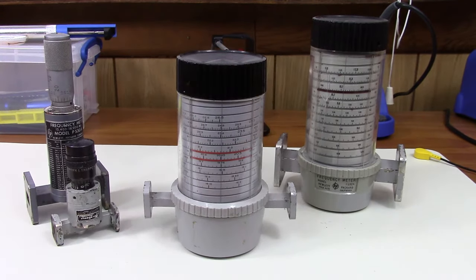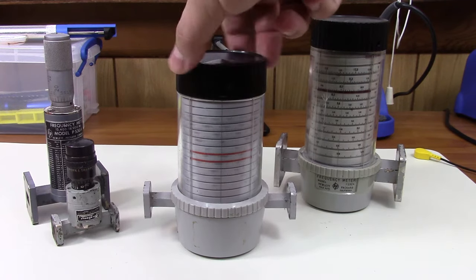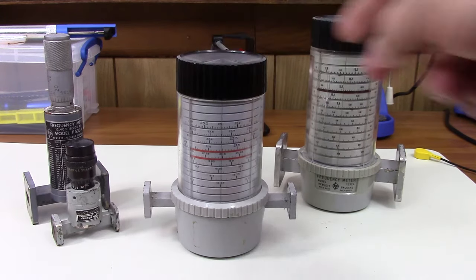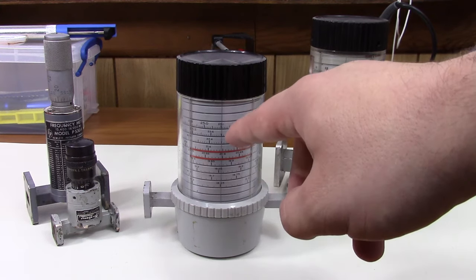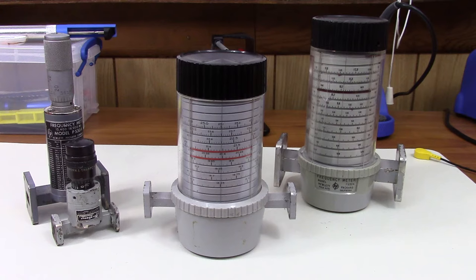So how do these frequency meters work? Well the principle is actually quite simple. They are basically tuned cavities, and as you change this knob up here you're changing the resonance frequency of the cavity inside and you're also spinning around the scale on which you will be able to read that resonance frequency.